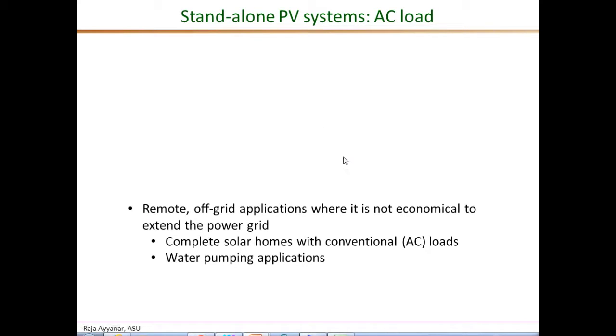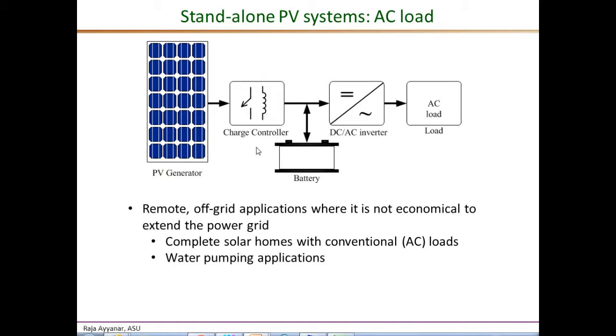Then we have standalone PV inverters supporting the more common AC loads. Applications could be any off-grid load — for example, in remote places it may be more economical to support the entire load through PV systems rather than extending the power grid. The configuration once again requires battery energy storage and a charge controller. The PV or battery DC voltage is converted to sinusoidal AC voltage through a DC-to-AC inverter, which maintains the voltage magnitude and frequency within the limits required by the AC loads.